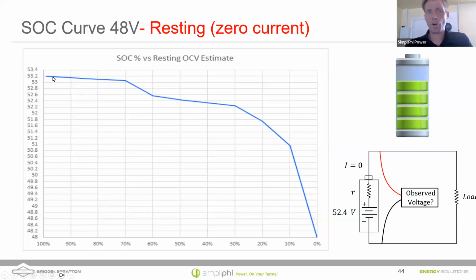Don't be confused. We charge up to 56 volts. That's the charging equipment's voltage, right? As soon as that charging equipment stops the charge cycle, it will come down to the voltage of the battery. And it takes a few minutes maybe to come down. So you're going to charge up to 56 volts, but once we disconnect the charging equipment, you'll start off here around 53 to 54 volts fully charged.